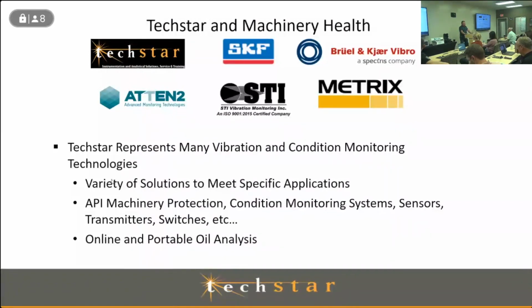The two primary product lines that we carry for online monitoring would be SKF and BK Vibro. SKF is more general purpose type monitoring. They do a lot of wireless. They do a lot of smaller type monitoring systems but still provide you the dynamic data for analysis and so forth. BK Vibro is more of your API-based machinery protection systems, similar to what you would have on more critical machinery, where you use the relays of the system to trip the machine offline.